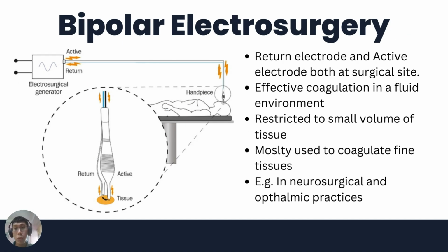In bipolar electrosurgery, the active and return electrode functions are both positioned at the surgical site, using the tips of the forceps. The forceps' two tips serve as the active and the return electrodes, and the only tissue that is grabbed within the forceps is part of the electrical circuit. Hence, one tip of the forceps handles the return function. A separate patient return electrode is not required.